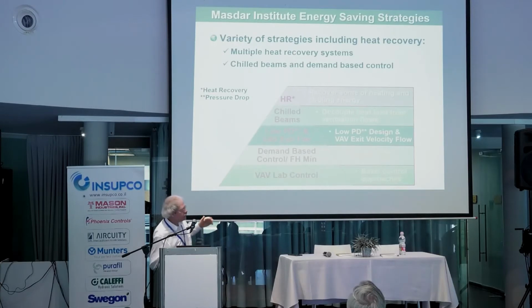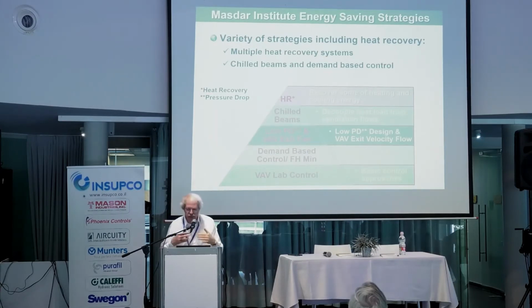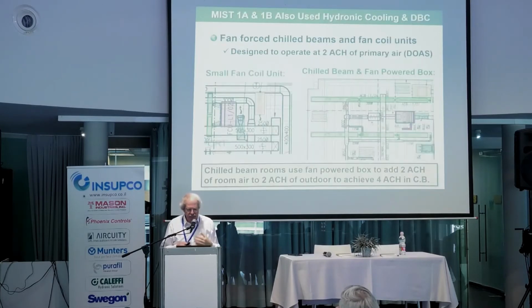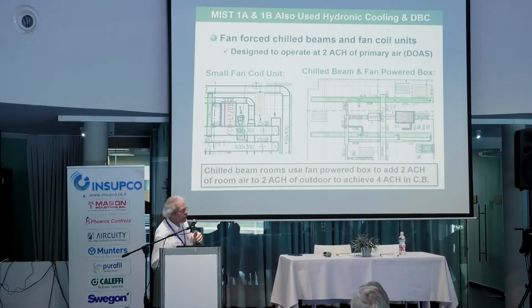So again, same sort of technologies. They obviously have variable volume lab controls. Then the demand-based controls, lower fume hood minimums based on new requirements that have come out around that time. These are some of the laboratory ventilation requirements. Again, using low pressure drop design, varying exhaust fan velocities with some techniques. Chill beams again, common theme, and lastly heat recovery. So these are the classic approaches that people are using. And they were using a combination. In some labs they had chill beams, in other labs they had fan coil units. So again, same idea.